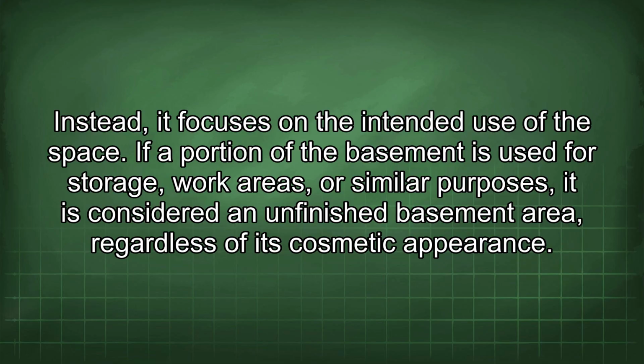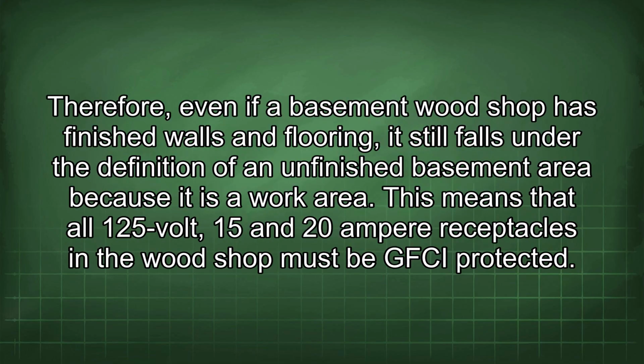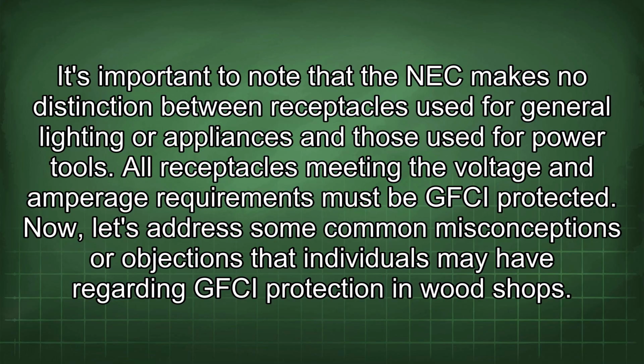If a portion of the basement is used for storage, work areas, or similar purposes, it is considered an unfinished basement area, regardless of its cosmetic appearance. Therefore, even if a basement wood shop has finished walls and flooring, it still falls under the definition of an unfinished basement area because it is a work area. This means that all 125-volt, 15 and 20 ampere receptacles in the wood shop must be GFCI protected. It's important to note that the NEC makes no distinction between receptacles used for general lighting or appliances and those used for power tools. All receptacles meeting the voltage and amperage requirements must be GFCI protected.